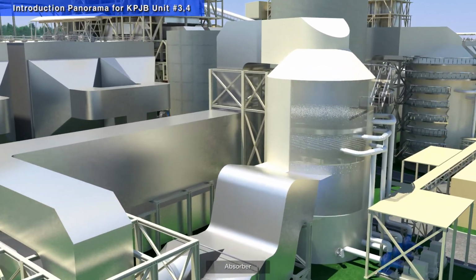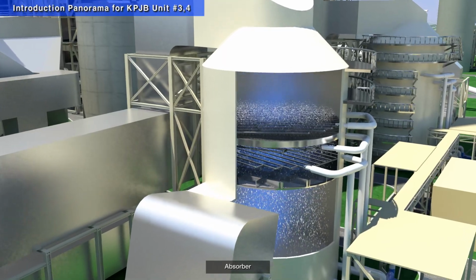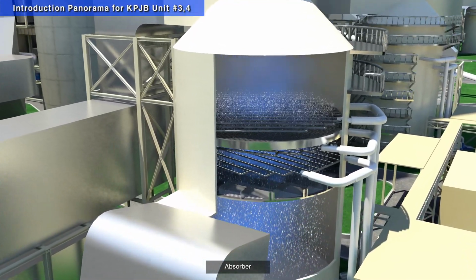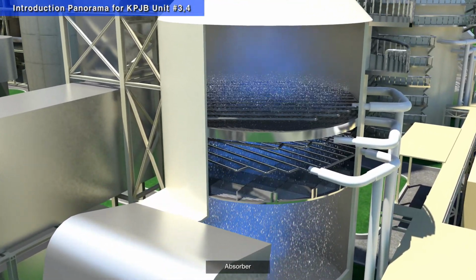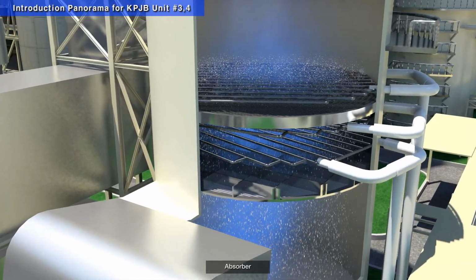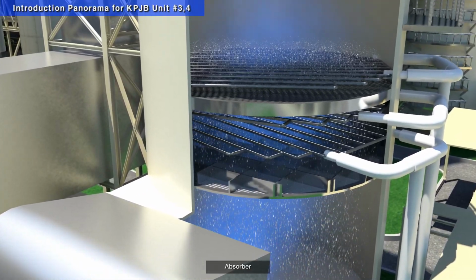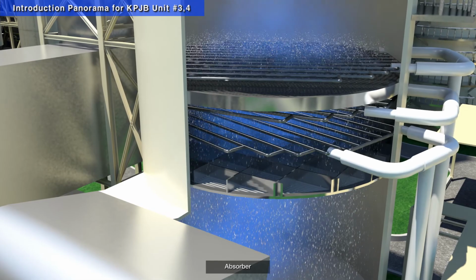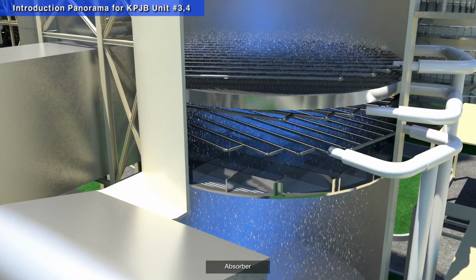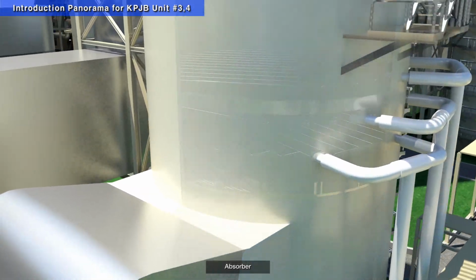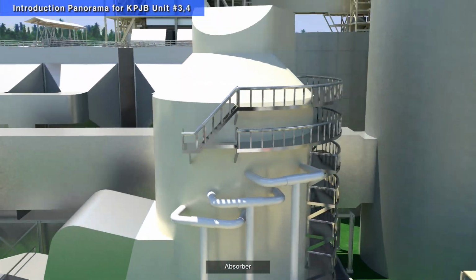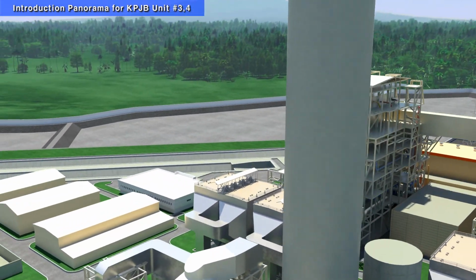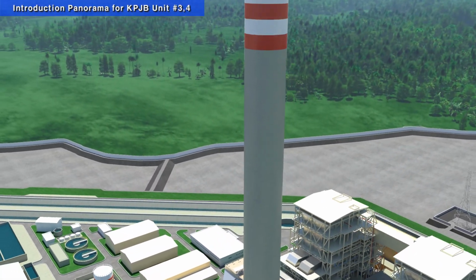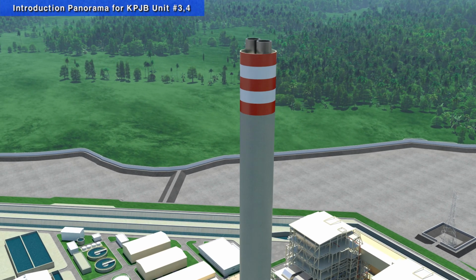Sulfur dioxide of the exhaust is removed by the flue gas desulfurization. By passing the boiler exhaust gas through the absorber, the sulfur dioxide gas of the exhaust gas and the limestone slurry which is sprayed from the top of the absorption tower react with each other, so that the slurry absorbs the sulfur dioxide gas and thus discharges the clean gas without sulfur dioxide.